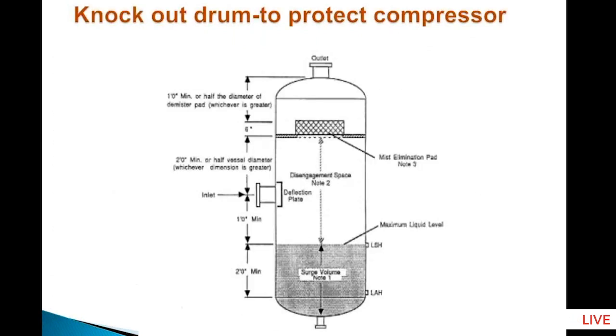Now we come to the next vessel, which is the knockout vessel, knockout drum. Knockout drum is a protection vessel. It is not compulsory in the system. If you design the system well, there is no need to have a knockout drum. But wherever you are having problems in the system, liquid coming to the compressor, insert a knockout drum. A knockout drum is inserted between the evaporator outlet and the compressor suction. It is kept in the machine room.